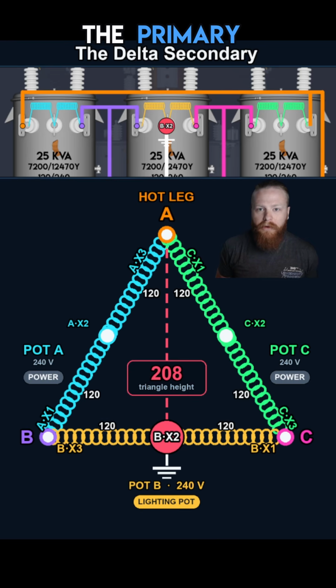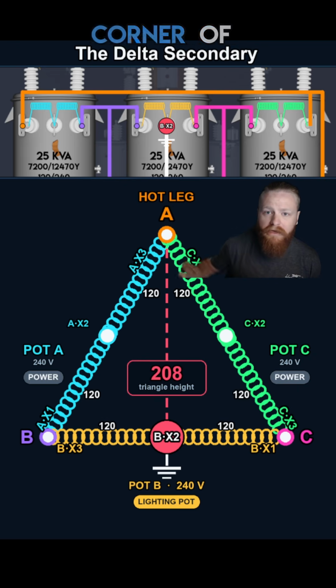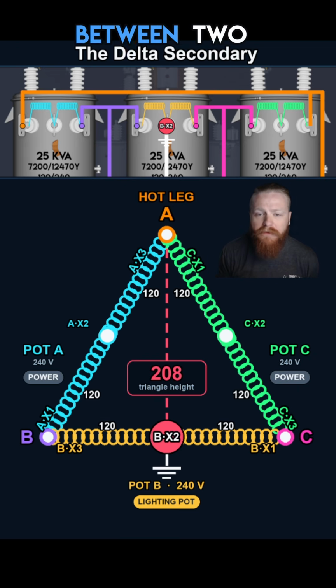Let's forget about the primary wiring and dive straight into a closed delta secondary. Three pots wired corner to corner into a triangle. You can see each pot's coil above and below, and each corner of the triangle is just the wiring between two transformers. Each pot has two coils rated at 120 volts each, or 240 volts across both in series.